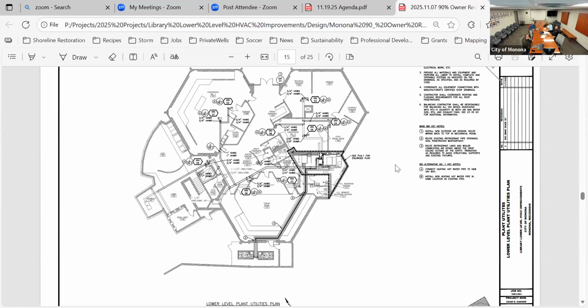One of the things we found during design, in our investigations, is that the air handler fan motors and the airflow being pushed into the lower level is not adequate. So basically we're getting too low of pressure in the lower level, which is causing the upper level to push air down the stairwell. And when they built that gigantic stairwell, which was after the addition, they didn't account for any of that within the HVAC system.